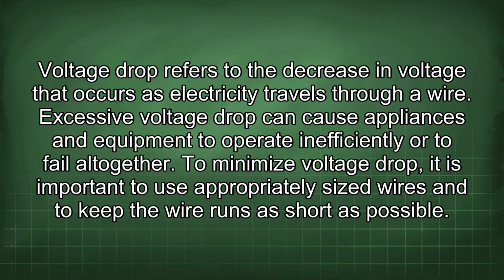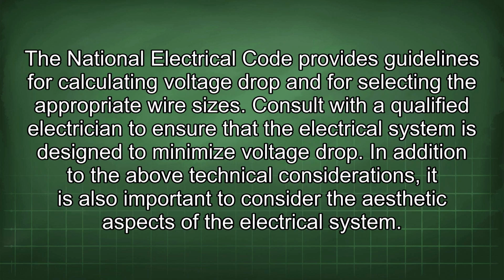Voltage drop refers to the decrease in voltage that occurs as electricity travels through a wire. Excessive voltage drop can cause appliances and equipment to operate inefficiently or to fail altogether. To minimize voltage drop, it is important to use appropriately sized wires and to keep the wire runs as short as possible. The National Electrical Code provides guidelines for calculating voltage drop and for selecting the appropriate wire sizes. Consult with a qualified electrician to ensure that the electrical system is designed to minimize voltage drop.